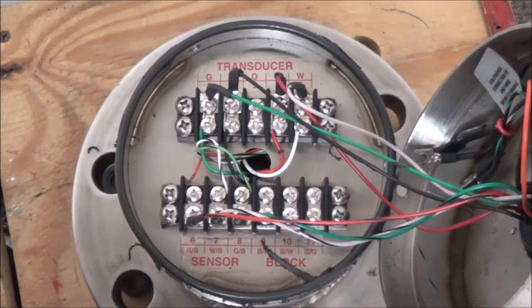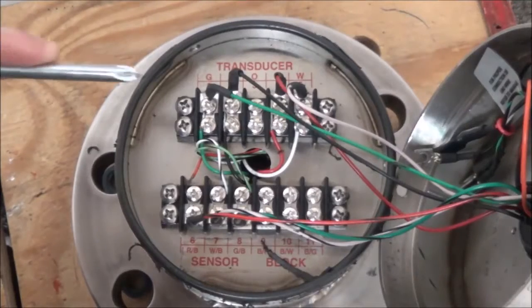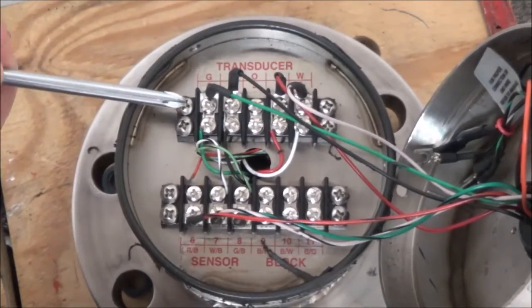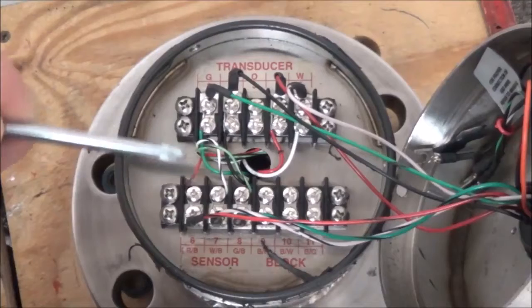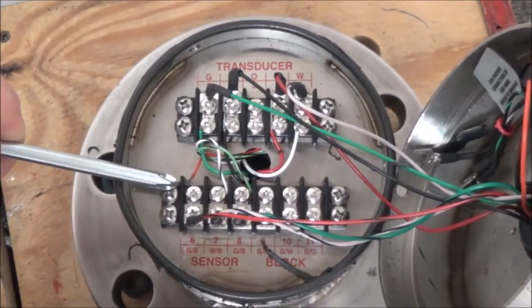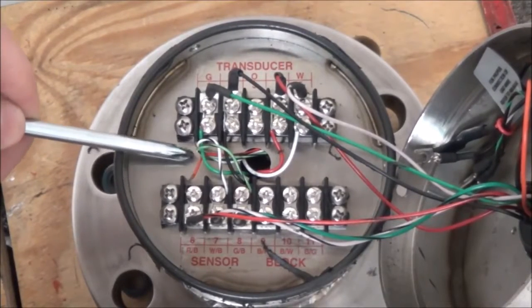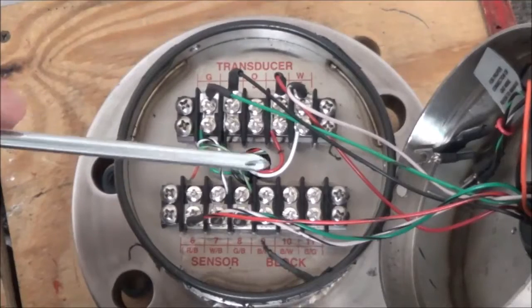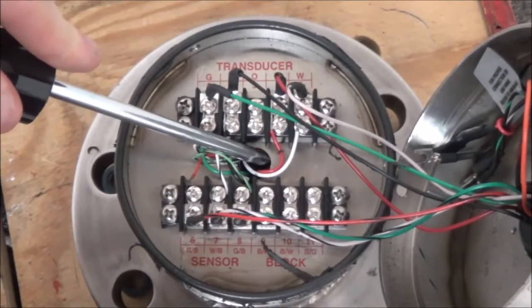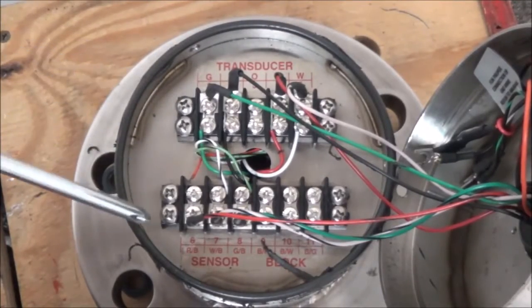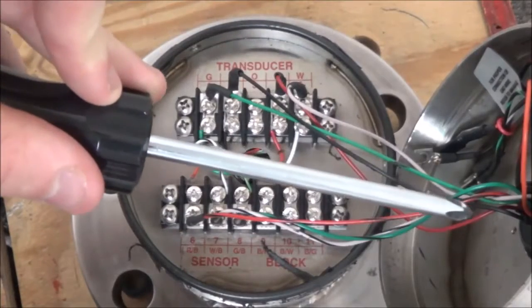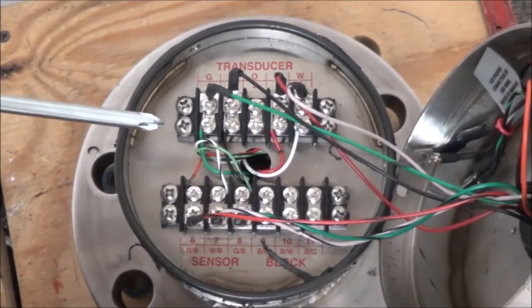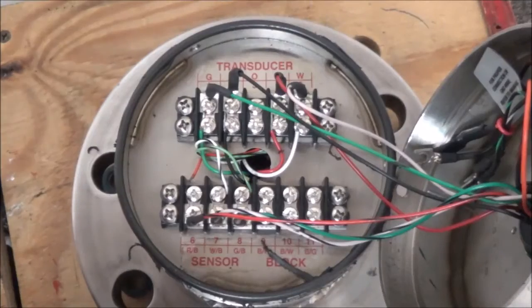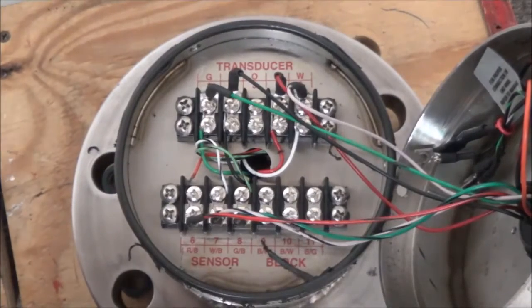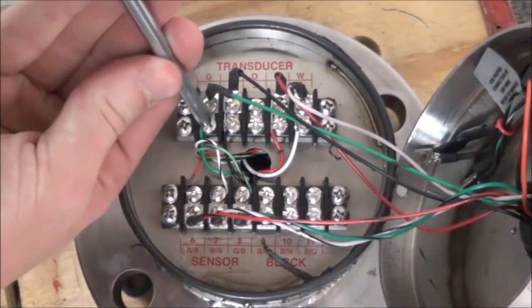There are 2 terminal blocks hidden underneath the transducer. The outermost terminals are reserved for the transducer we just removed, while the innermost terminals are reserved for the wires that go into the sensor block. Since it is very difficult to get to the sensor block without removing all of the inner wires, all of the inner wires in the innermost terminals must be removed.